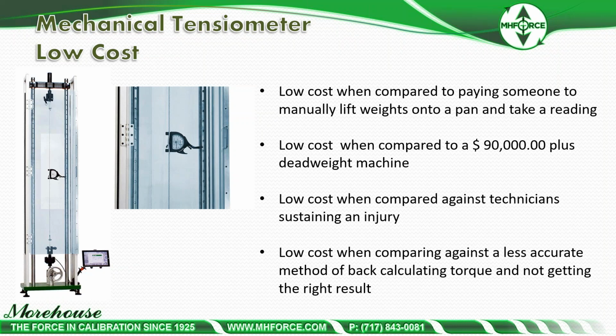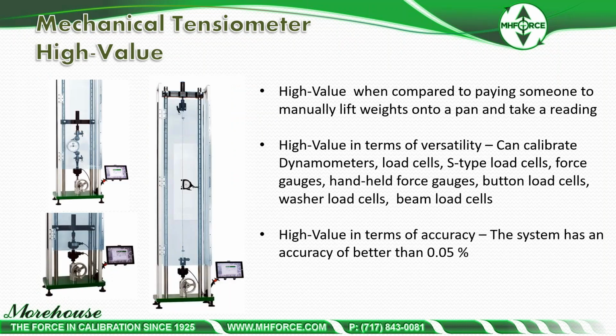Typically, the dead weight version of these tensiometers is about 90,000 plus, so this one's a lot lower cost than that. Low cost against injury, low cost when compared against a less accurate method of back calculating torque and not getting the right result. Again, I'm not a fan of back calculating torque. You cannot convince me that works. I need to come see that and take readings, and I can poke holes in it all day long. High value when compared to paying someone to manually lift weights onto a pan.